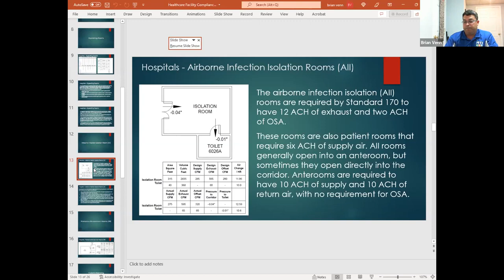So obviously these rooms need to maintain a negative pressure at all times, for the health of the residents and workers of the hospital and to contain the patient in these rooms. Per standard, again ASHRAE 170, we're looking for 12 air changes of exhaust on this side, because again, we're looking to establish a negative isolation environment. So we need the exhaust number to drive that boat. So 12 air changes of exhaust and then 2 of outside air. So we still need to read and record the supply air changes for this room so that we can mathematically come up with how many air changes of outside air we have.